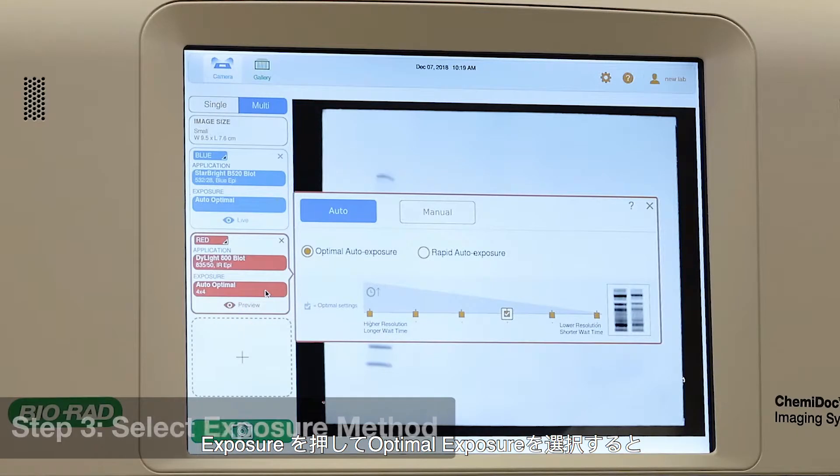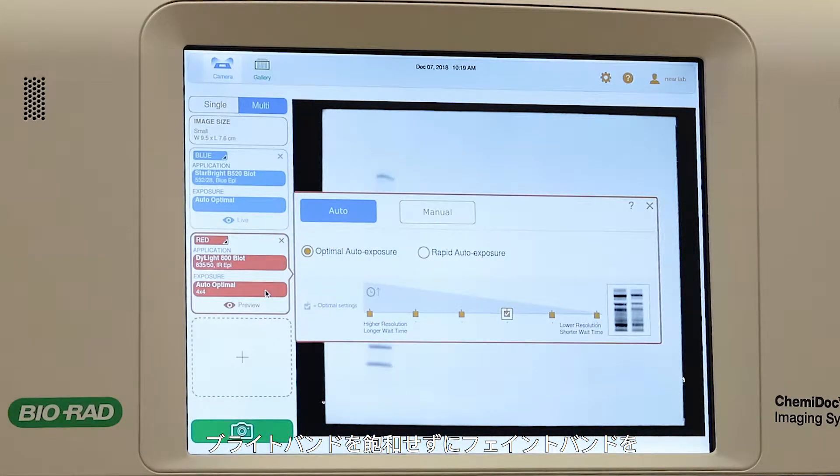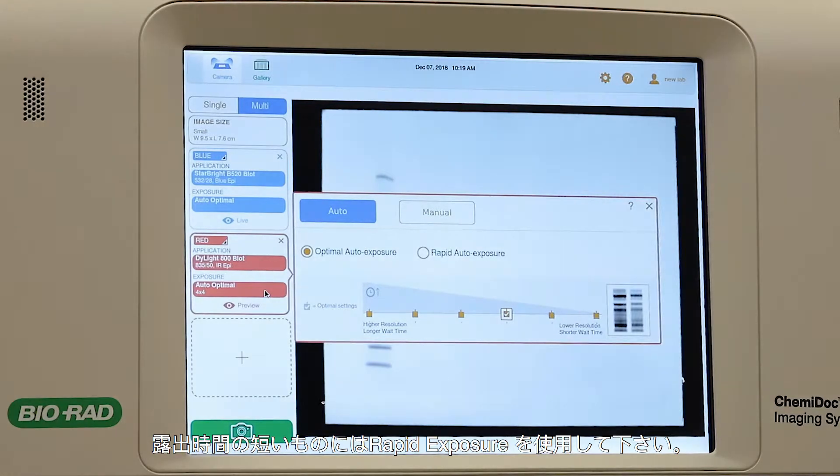Tap Exposure. Select Optimal Exposure to use the full dynamic range of the instrument to show faint bands without saturating bright bands. Use Rapid Exposure for shorter exposure times.